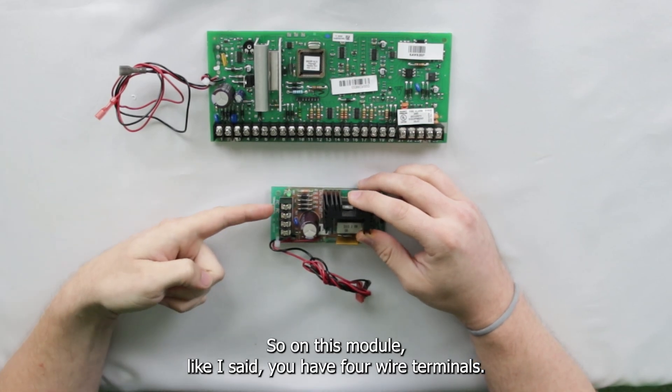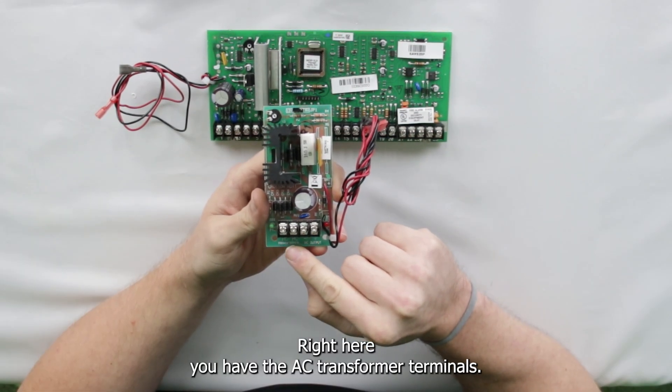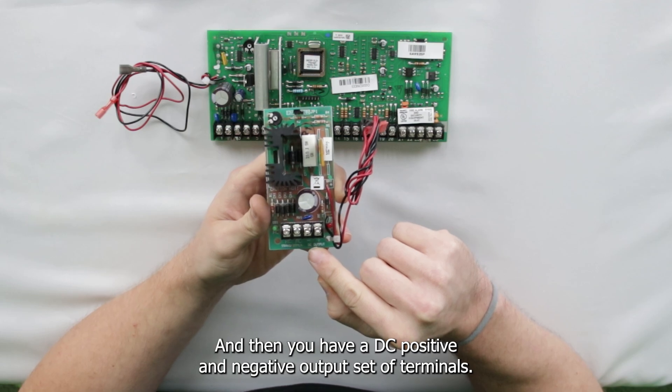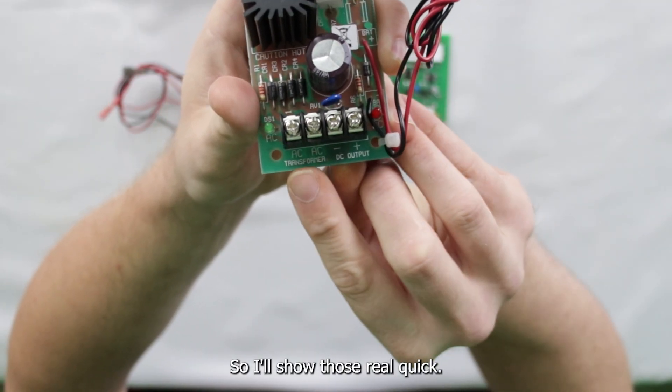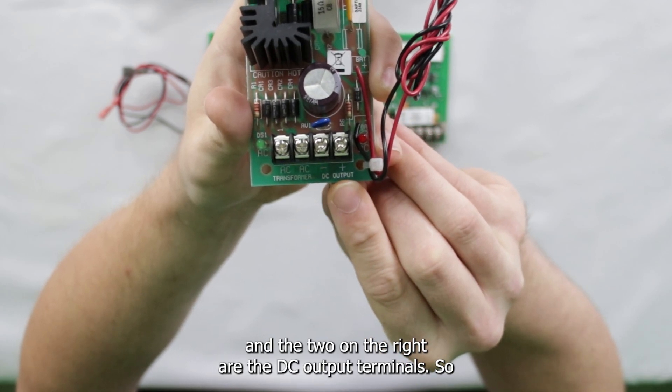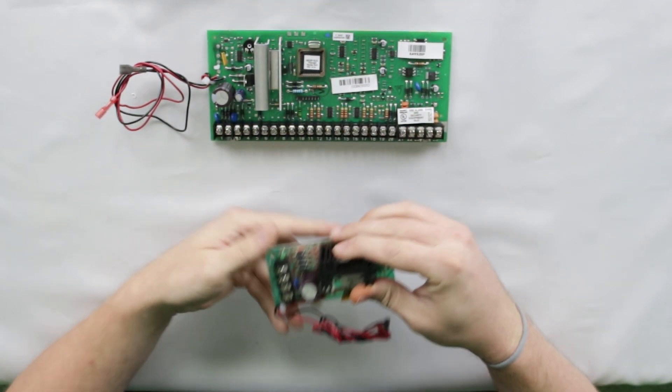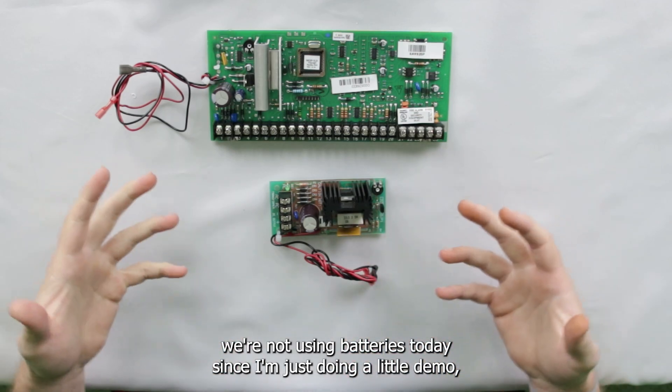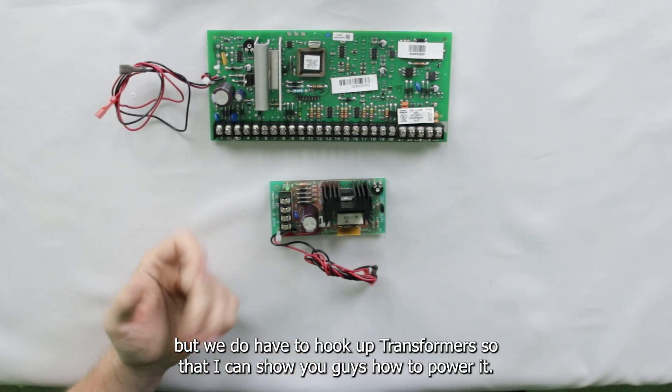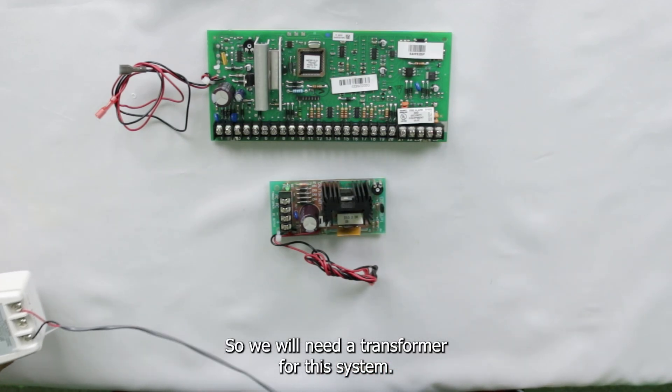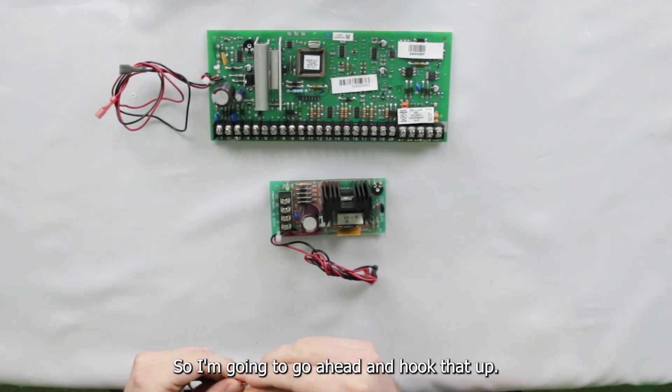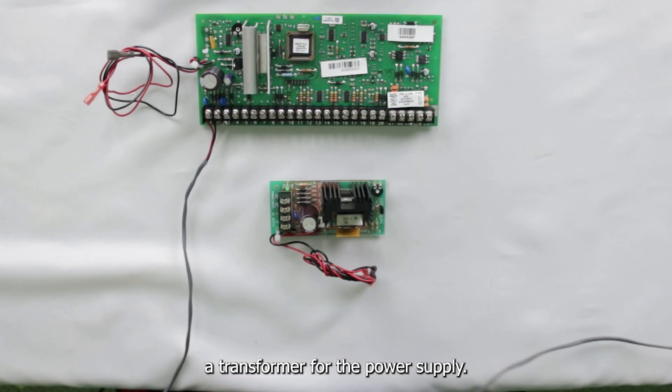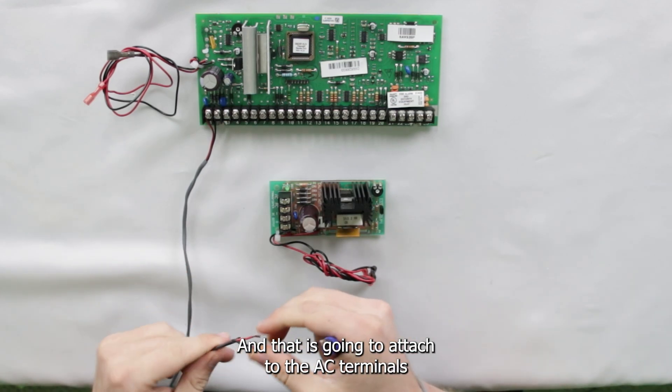So on this module, you have four wire terminals. Right here, you have the AC transformer terminals, and then you have a DC positive and negative output set of terminals. So the two on the left are the AC terminals, and the two on the right are the DC output terminals. As I mentioned, you will need a transformer and a battery with this. We're not using batteries today since I'm just doing a little demo, but we do have to hook up transformers so that I can show you guys how to power it. So we will need a transformer for the system, and then we will also need a transformer for the power supply that is going to attach to the AC terminals here.